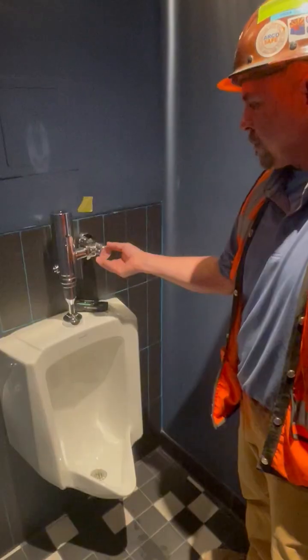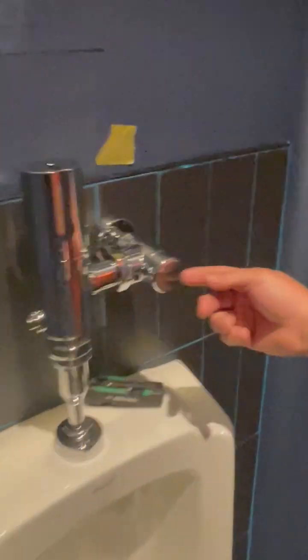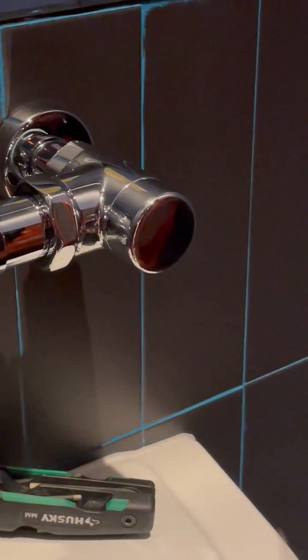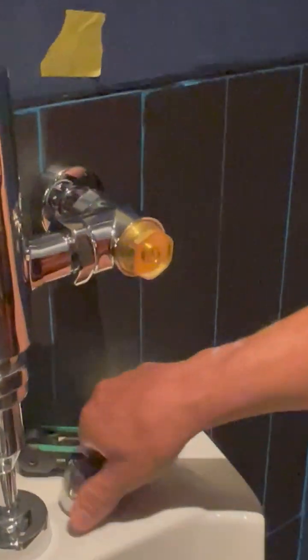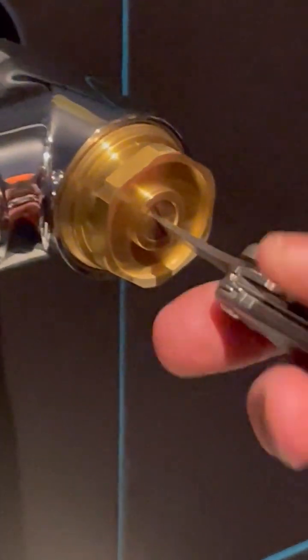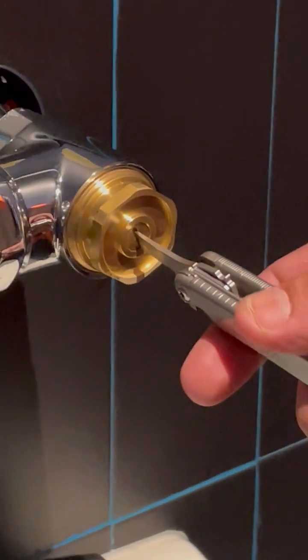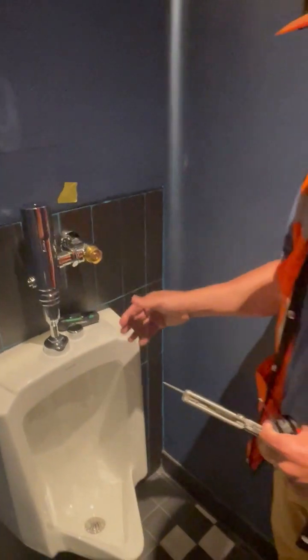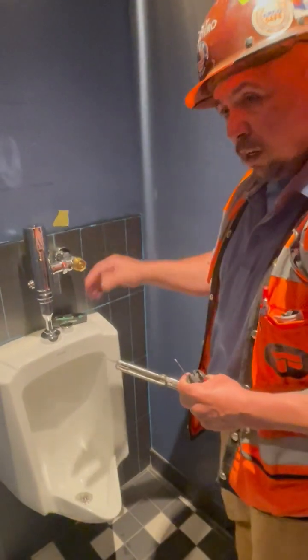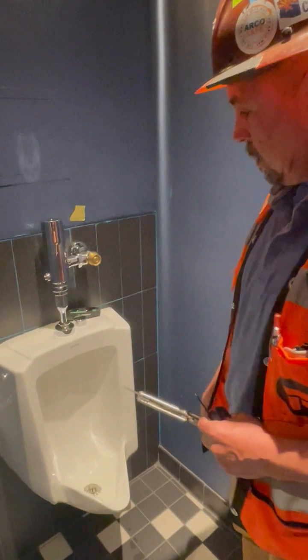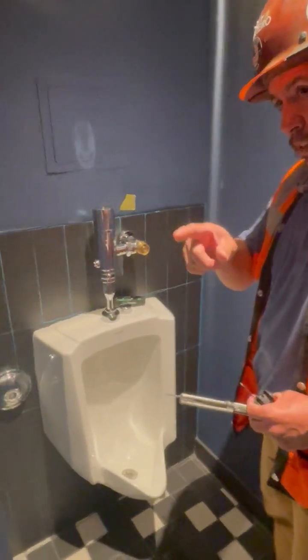Cool. Right. Underneath this chrome cap, there's an Allen screw. You remove the Allen screw with an Allen wrench, pop this off, and you can service this with a flathead screwdriver. Turn it clockwise to turn this fixture off, this flushometer, and that'll kill one individual fixture instead of having your entire restroom down. And then this can be serviced and worked on. And then the faucets in the men's room, we're still in the men's room, lower level. Underneath there's some service valves, hot and cold water, angle stops on the bottom. That'll kill this fixture alone by itself without turning the main off and shutting down the whole restroom.